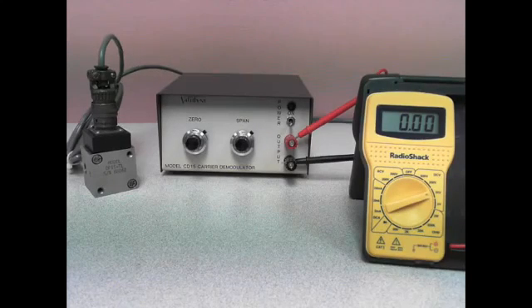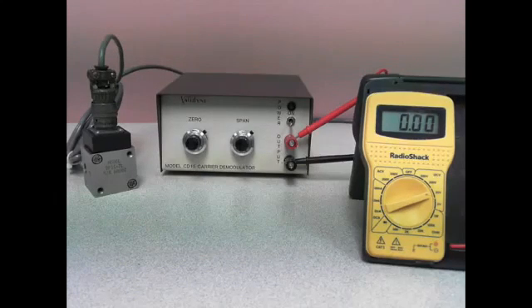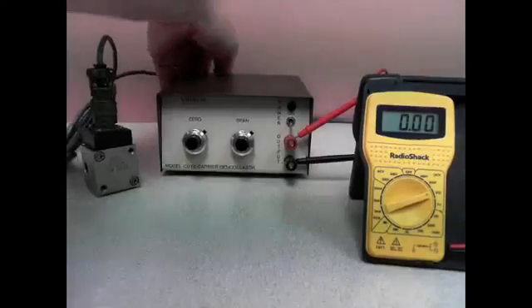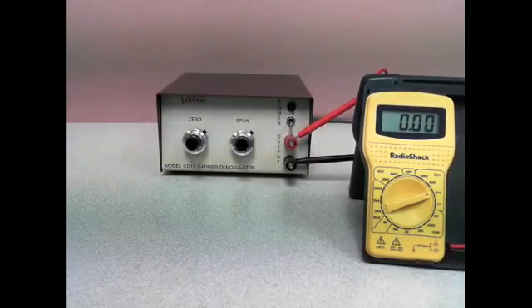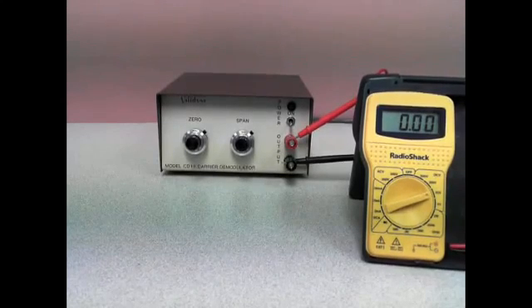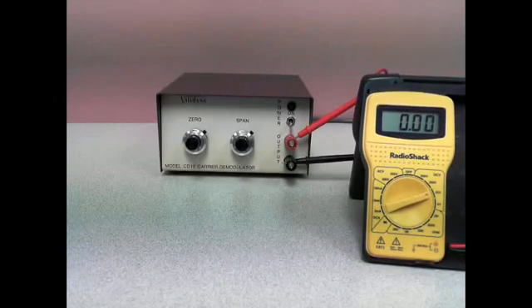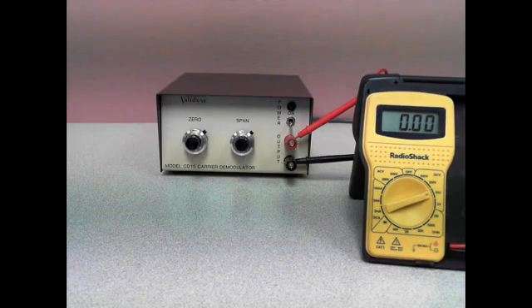In order to check the CD15, we first remove the DP15 cable that is connected to the rear panel of the CD15. As you can see, we've connected a simple multimeter to the CD15 output binding posts to be able to read the analog output. Black lead connects to the black binding post and the red multimeter lead connects to the red binding post.